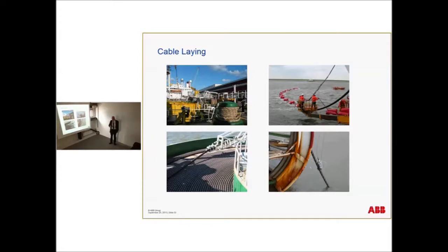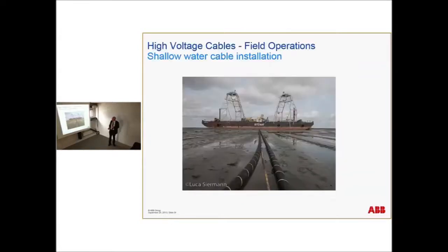So you need good weather conditions. And we normally talk about weather windows for laying cables. In the North Sea, it's in the summer. Now it's too late, with the storms and everything. So we need to produce the cable all over the year. Then it's loaded from May to August, and then they do the installation works from May to September. You can see also shallow water cable installation. Then you have to pull the cable from sea to shore.